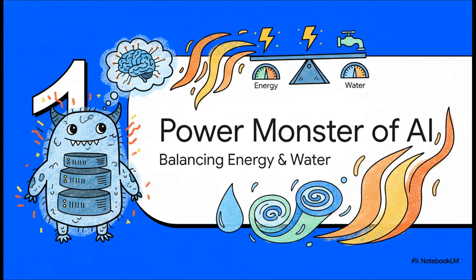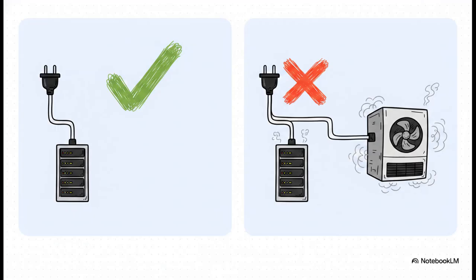Section 1: the power monster of AI, and how we balance energy and water. To wrap our heads around this energy challenge, we use a metric called PUE, or Power Usage Effectiveness. The ideal PUE is 1.0, meaning every watt pulled from the grid goes straight into powering the servers—nothing wasted. An inefficient PUE of 2.0 or higher means a data center is wasting just as much power cooling the building as running the actual computers. In the age of AI, a PUE of 2.0 is an absolute disaster for the grid.